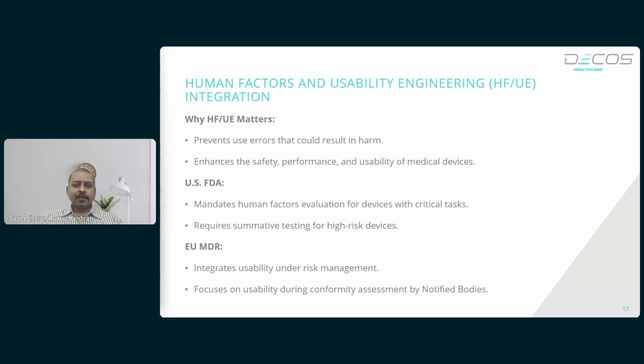Human factors engineering must demonstrate that the devices can be used safely and effectively, aligned with FDA guidance, for example, FDA's guidance for applying human factors and usability engineering. Summative usability testing is often required to confirm that critical tasks are performed without causing harm or error.